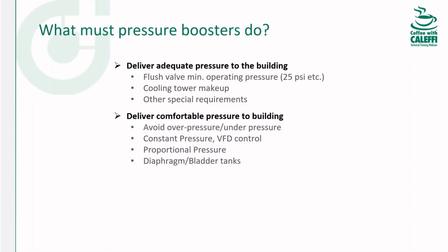Next, we want the pressure boosters to deliver comfortable pressure to the building. Obviously comfort implies people, so we don't want too much and we don't want too little. And in today's world, booster systems are pretty much supplying constant pressure, using a constant pressure control mode, to the building through the use of VFDs, or variable frequency drives. Variable speed pumping is probably a class all by itself, so we won't really get into that too much. Other tactics to assist with comfort might be advanced controllers that can do proportional pressure algorithms. And we can also use diaphragm tanks and bladder tanks, which help smooth out the peaks and valleys.